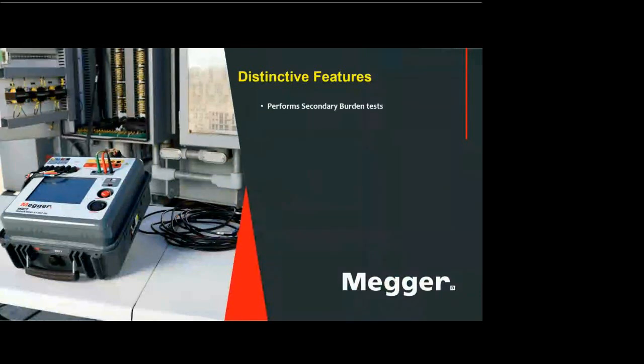Another thing, it can perform a secondary burden test. When we say secondary burden test, we are trying to test the actual burden of the CT, right? The actual load of the CT here. So for example, if you have a relay or a meter connected to the CT, then we can measure the actual ohms or the actual VA of that burden. And so we can change the setting, or put into the calculation, oh, this is my actual burden, what will be my accuracy on that burden? So you can put that in the nameplate value.